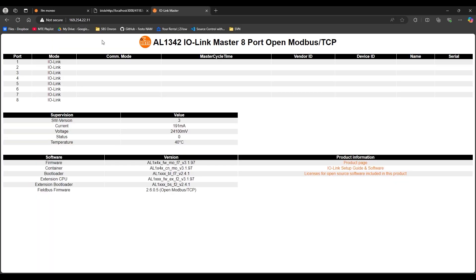If I actually go back to, not Moneo, but if I type in the IP address of our IO-Link port into a new tab on my web browser, you can see that at port one here, I can see the web server for the IoT port. At port one here, I'm not detecting any device, so I'm not going to be able to perform any kind of field bus communications over that Modbus TCP port, nothing's going to work here.